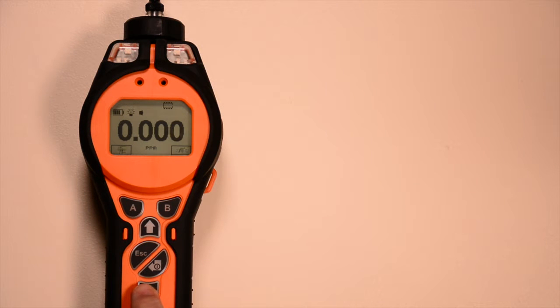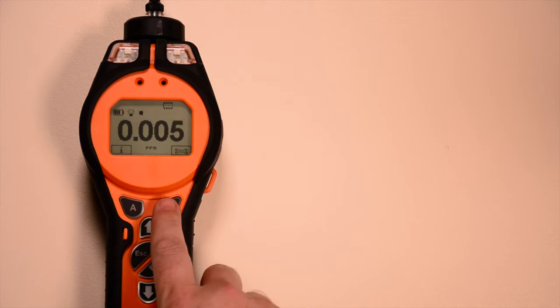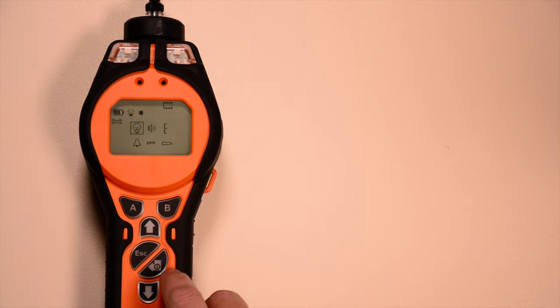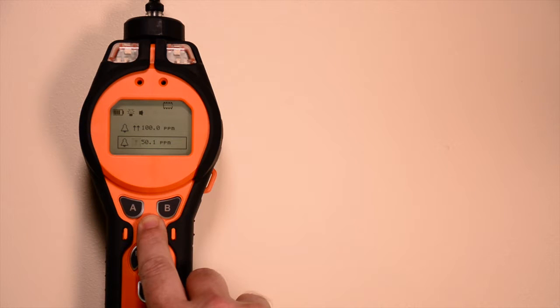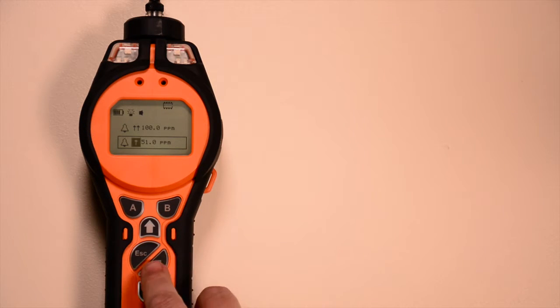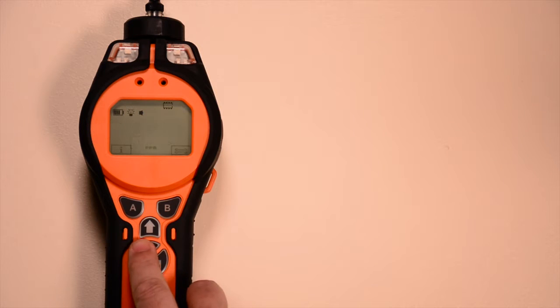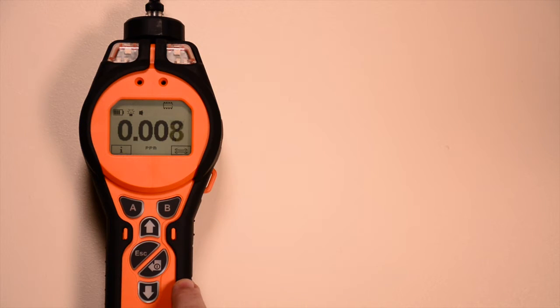To adjust the alarms, use the up and down keys to find the setting symbol and press the soft key to select it. Use the up and down keys to choose the alarm bell symbol and press Enter. Select the alarm to be adjusted using the up and down keys and press Enter. When the arrows flash, the value can be adjusted using the up and down keys. Press Enter to select the value. Then press Escape twice to return to the main screen. This procedure is used for both high and low alarms.